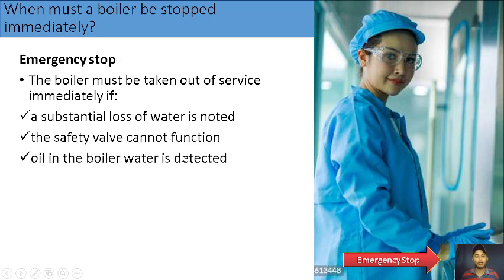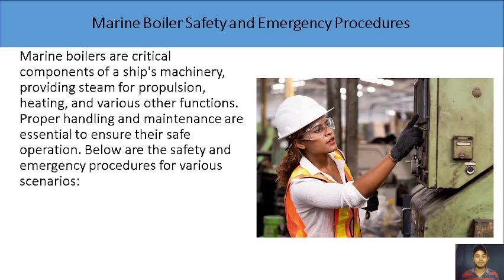Next, if oil in the boiler water is detected. If there is oil in the boiler water, you should stop the boiler, remove the oil, and inspect where that oil came from. Next, if too high a salinity level is detected. If there is too much chloride or salinity in our water, you should stop it immediately to prevent scaling from building up inside the boiler, and then rectify the problem first before starting it again.